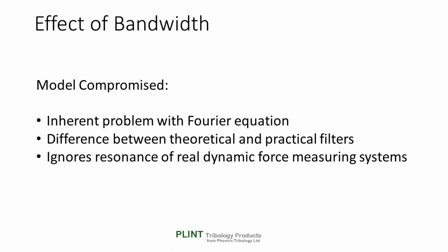This model is not bad as a fairly crude illustration of the effect of varying input frequency with a fixed signal bandwidth system, but it is by no means a perfect model for a real dynamic force measurement system. There are three reasons for this. The first is to do with the Fourier equation itself, the second to do with the difference between a theoretical and a practical filter, and the third to do with resonance of a real dynamic force measuring system.